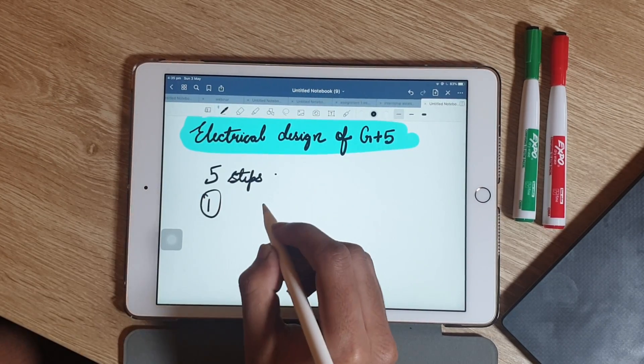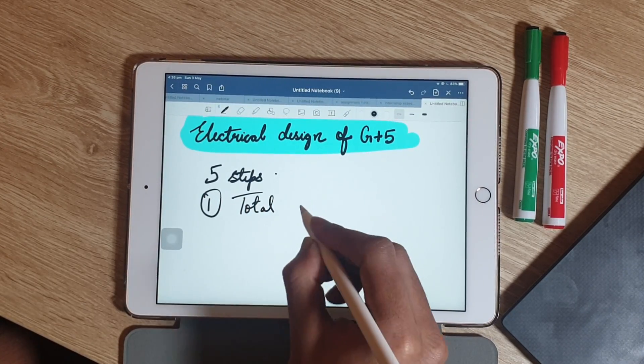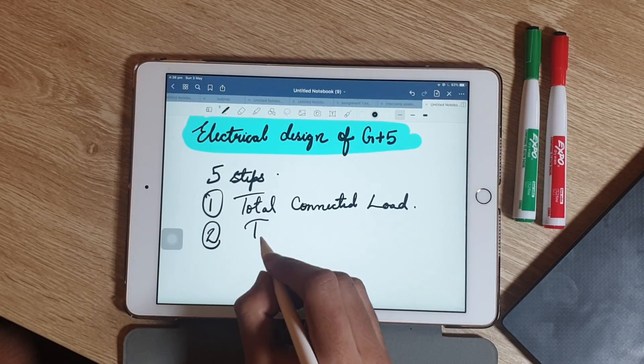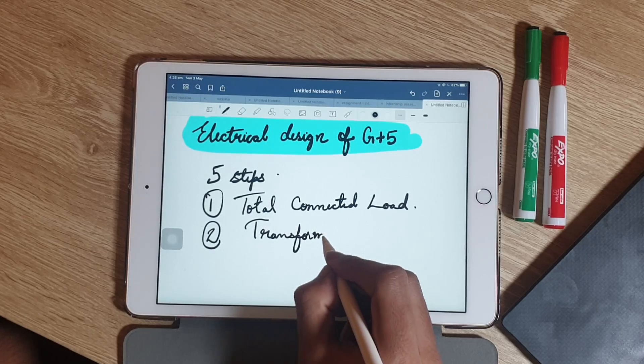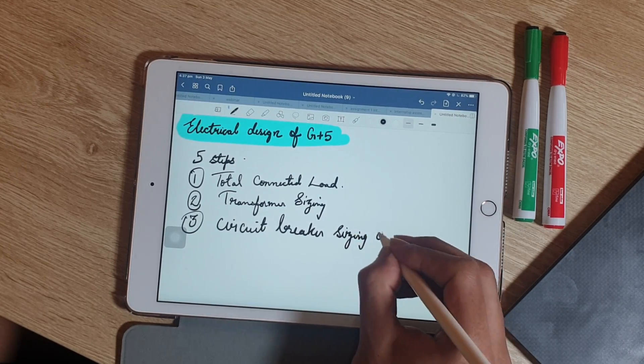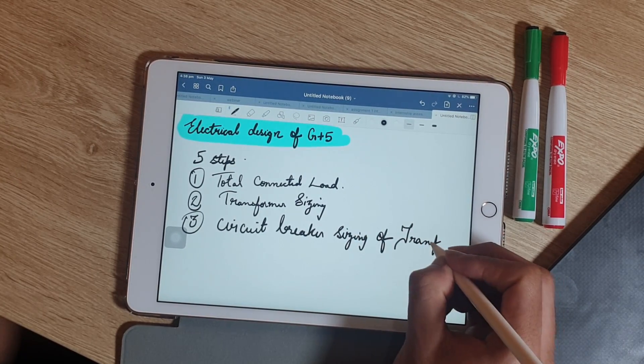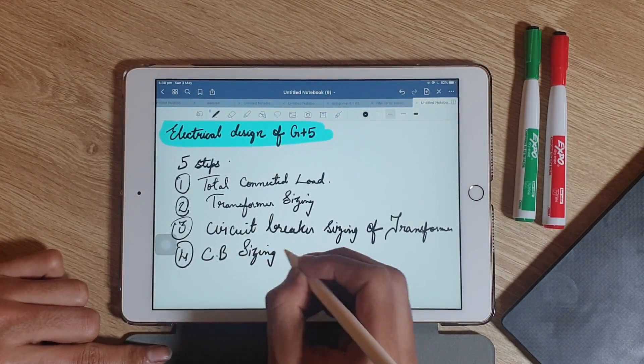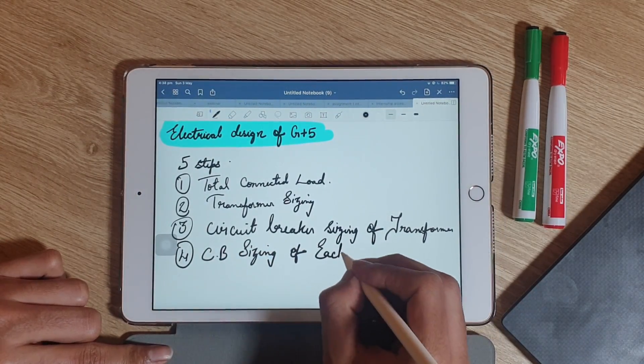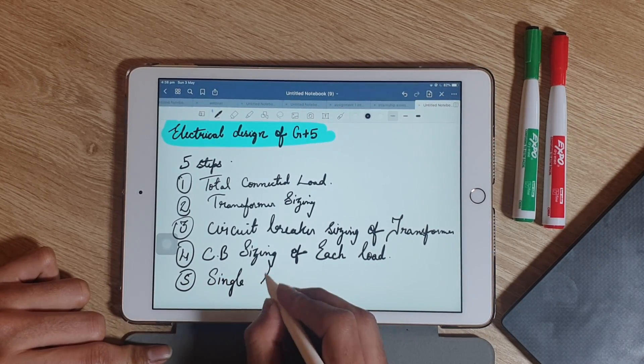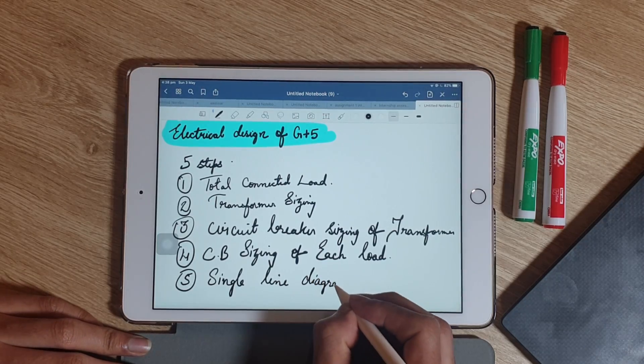For electrical designing of any building, it requires five steps. These five steps are: calculation of total connected load, transformer sizing, circuit breaker sizing on the transformer side for the main meter panel, circuit breaker sizing for each load such as flats, and preparation of a single line diagram, which we term as SLD.